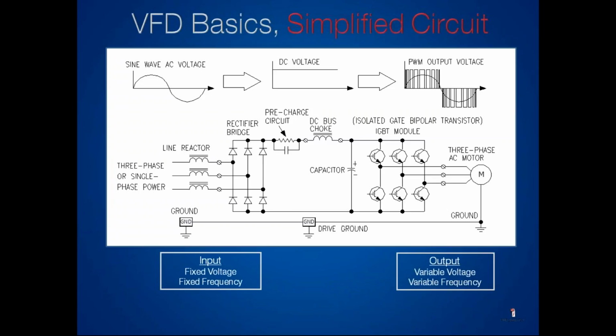So here is kind of exactly what's going on inside the VFD. Now this isn't critical. This is really just to give you guys a little peace of mind as to what's actually happening inside your drive. So you've got your AC voltage coming through. Let's say you've got 460 volts AC coming through. That AC voltage is hitting your rectifier bridge or diodes. Each one of these 6 little triangles that you can see on the left side of your drive are the diodes. Now what's happening at the diodes is we're converting that AC voltage to DC voltage.